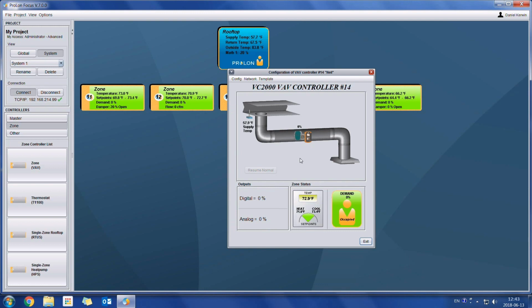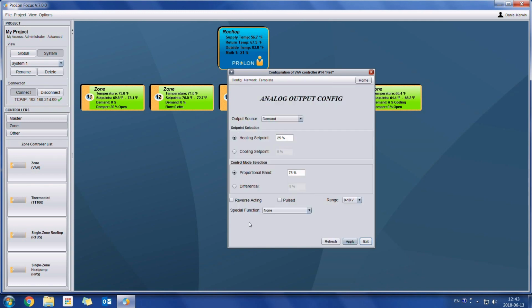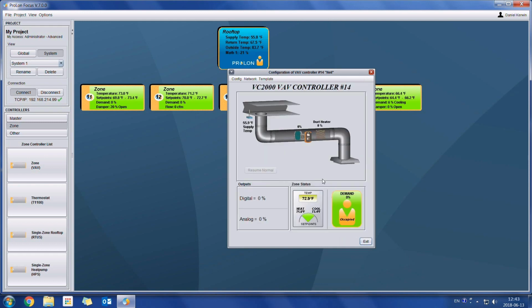Okay, now let's say I would like to configure something else. Let's say that this zone has a duct heater, and let's say it's a modulating duct heater. So I can simply go onto the analog output, double click. At the bottom here we have special function, so I'll put special function duct heater. We can choose what the voltage is, whether it's a 0 to 10 or a 2 to 10 volt range. I can press the apply button, and when I go back to the home page, we can see that the duct heater has just appeared. So the graphics will automatically adapt to your chosen sequence.